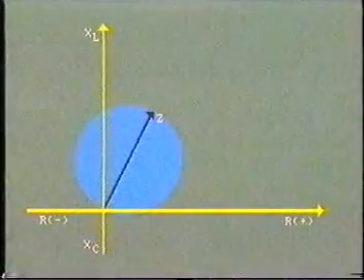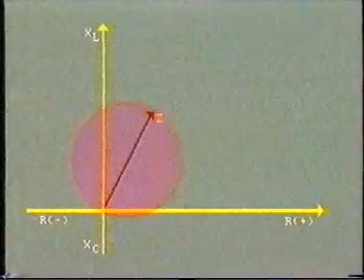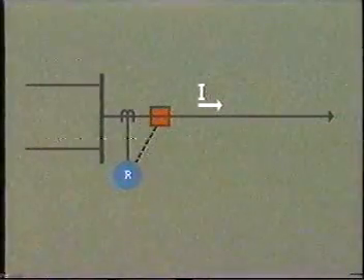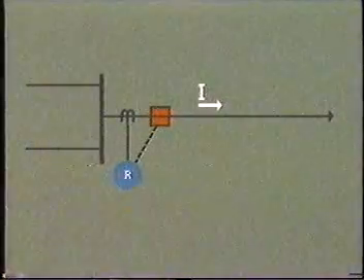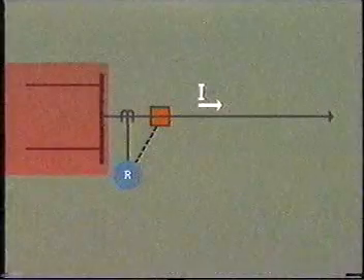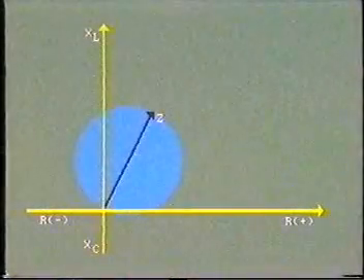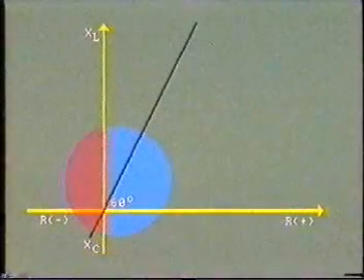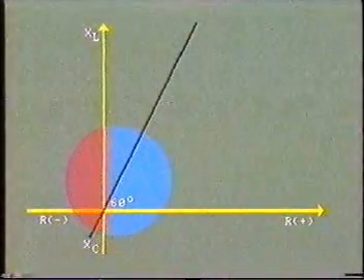Remember, this unit will only operate for faults within the circle. However, in some cases we may actually want the relay to operate as backup for close-in faults upstream. In this case, the characteristic can be offset like this, so that it will operate for very low impedance in the reverse direction.